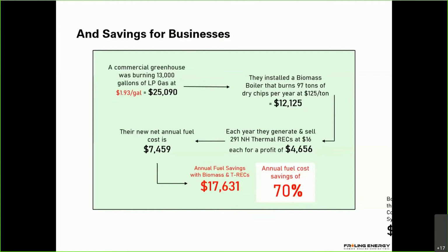Another one was a smaller setup, just 13,000 gallons of LP. And a gallon of LP is less BTUs than a gallon of oil, just for the sake of saying it. So this is a rather small system, but they ended up burning 97 tons instead of those 13,000 gallons. Again, this is the dry chips, and that's what we love, the dry chips. We'll say $12,000 for that. But now they're generating the thermal RECs, and $4,600 comes back net. Now, these often sell for about $20 apiece, maybe a little more, $22 or so, but there are fees and different things that come out of that. So a net of $16 is actually fairly average. Some do better, some do worse, I suppose. So their actual net is $7,400, and they have a $17,000 savings.